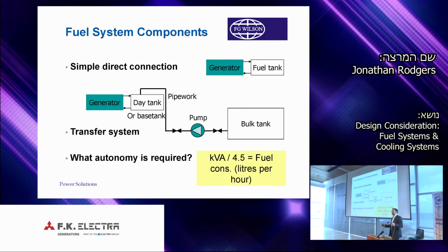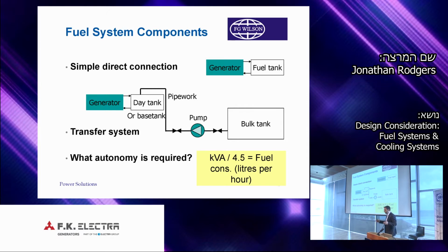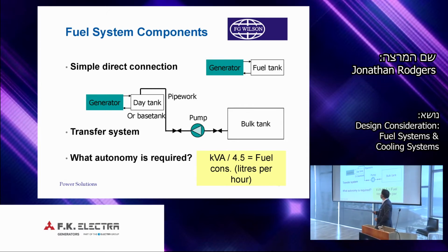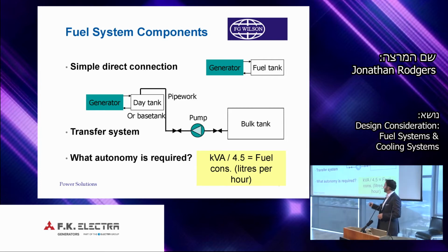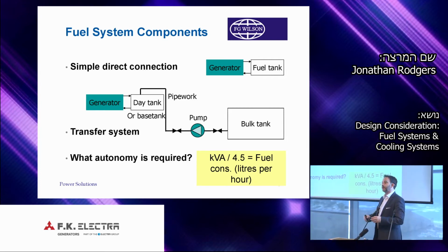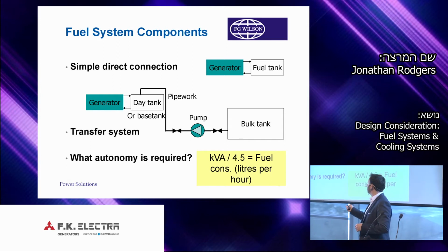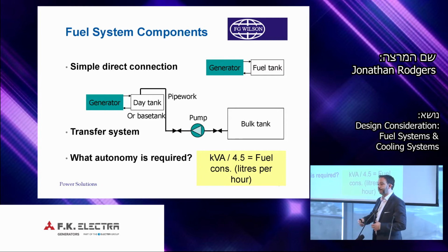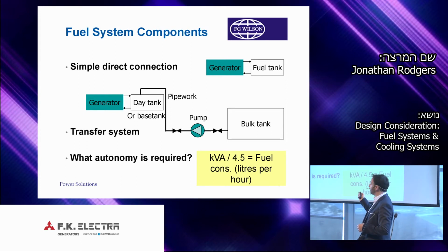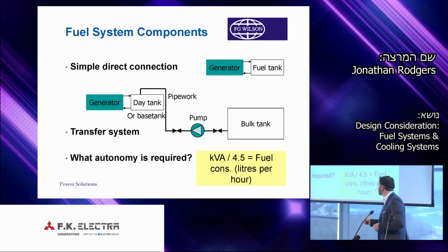So when we look at our fuel system, we typically have two basic types of fuel system. We have a direct connection where the generator and engine is directly connected to a local fuel tank. So this would be like our small mobile generators, typically. We also have systems normally for larger engines or for longer running hours, where we will have a local tank to the generator and then a bulk storage tank with additional fuel fill. In each case, the local tank always has a supply and return in every installation.